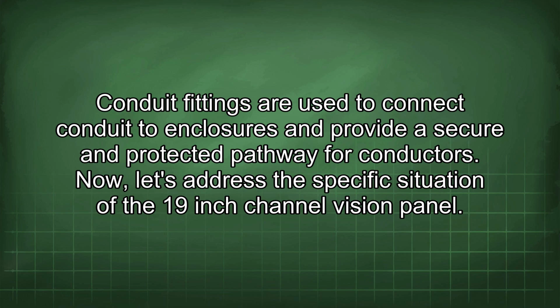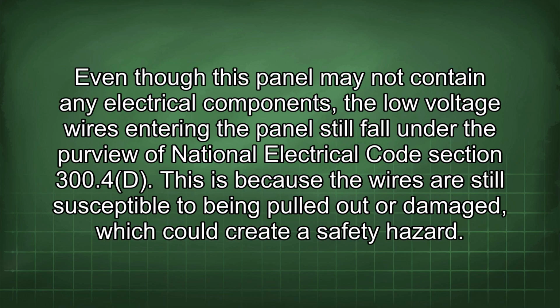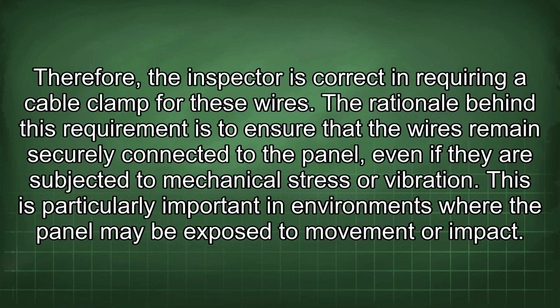Now let's address the specific situation of the 19-inch channel vision panel. Even though this panel may not contain any electrical components, the low voltage wires entering the panel still fall under the purview of National Electrical Code Section 300.4D. This is because the wires are still susceptible to being pulled out or damaged, which could create a safety hazard. Therefore, the inspector is correct in requiring a cable clamp for these wires. The rationale behind this requirement is to ensure that the wires remain securely connected to the panel, even if they are subjected to mechanical stress or vibration.